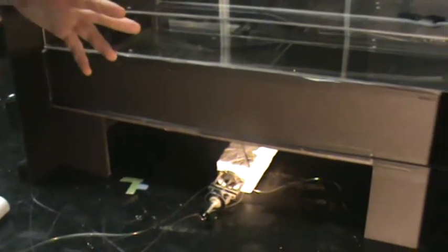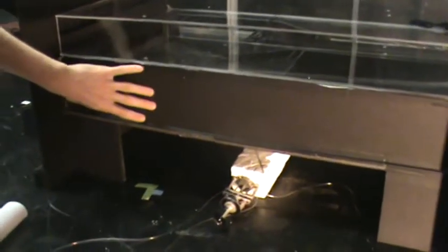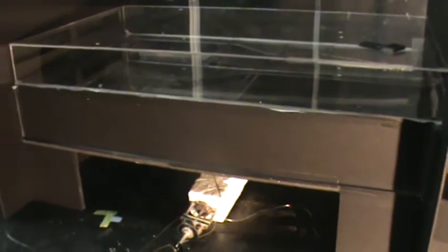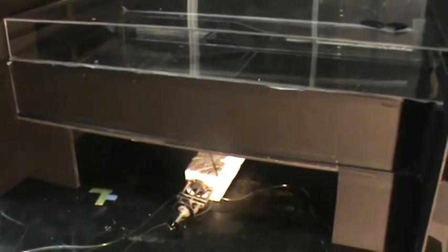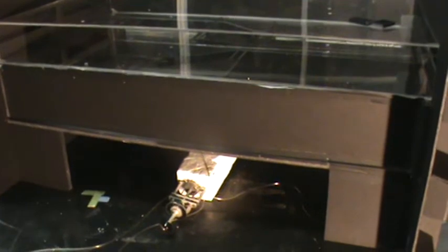But we'll check the pressure differences. So we have a way of translating from the airspeeds that we're measuring inside this model to an actual airspeed on the actual site. The goal of that is to see where we are in terms of the 10 air changes per hour. Because we've got a fixed volume of classroom and a fixed cross-sectional area of that duct, if we take that speed, we know exactly what the volumetric flow is, and we can figure out what the air change rate is.